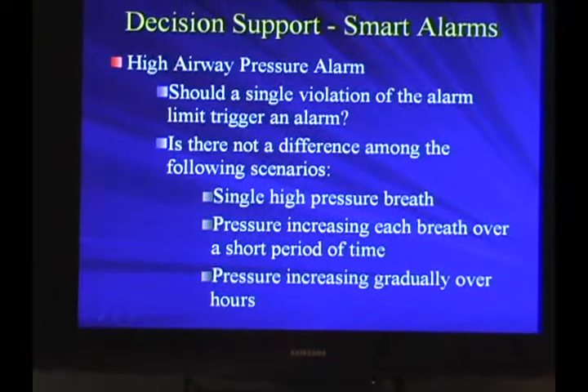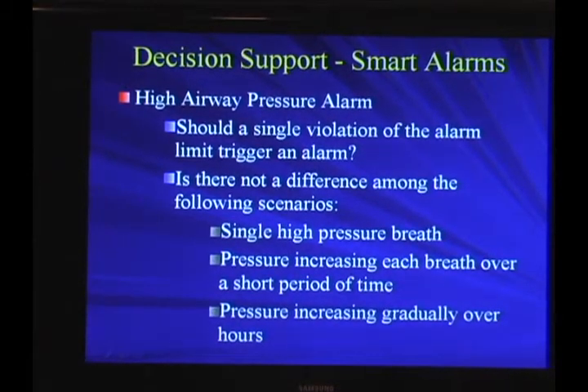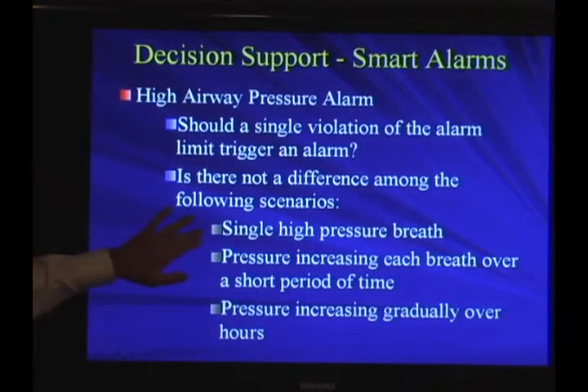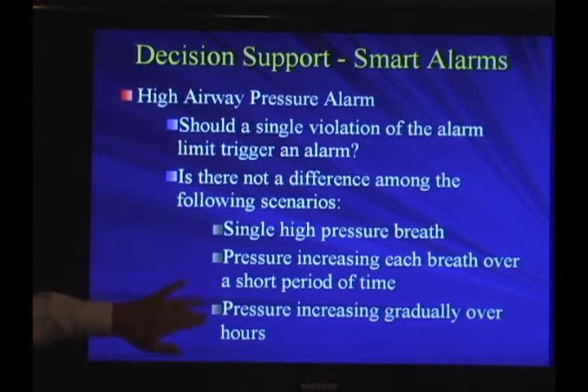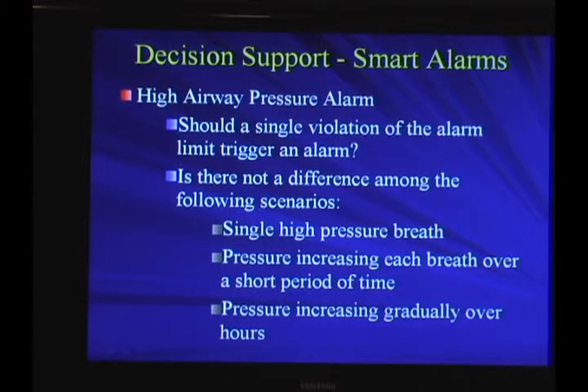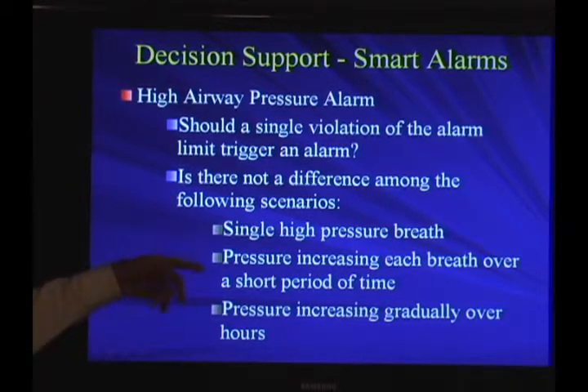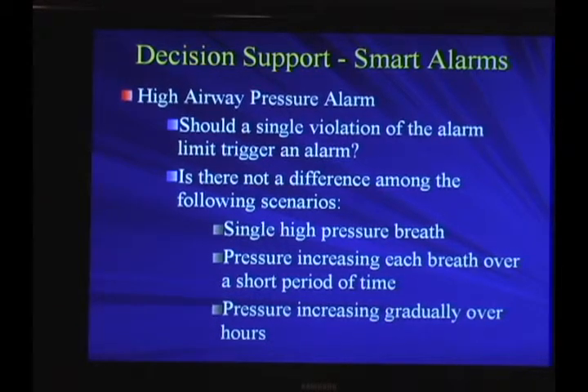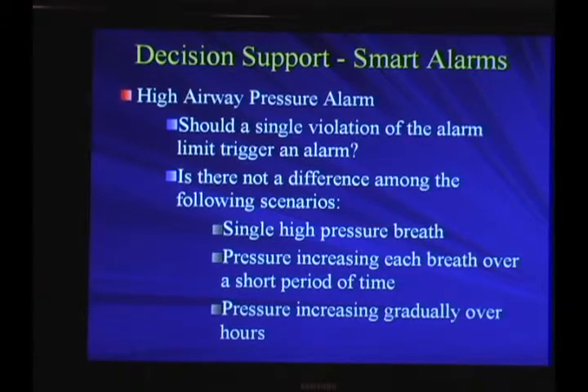screwy, we should have information that says this could be A, B, C, or D, and if it is, you should do A, B, C, or D in order to correct it, and that's not available today. If we just looked at high pressure alarm, going back to smart alarms for a second, if I had these 3 scenarios and gave you them, you would identify 3 different levels of seriousness of the problem. A single breath, that high pressure alarm once in a while, pressure increasing each breath over a short period of time, or pressure increasing gradually over hours. They represent to you very different scenarios and very different urgencies in which to respond to them.